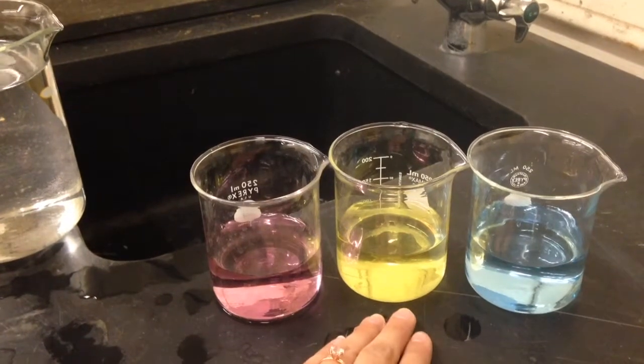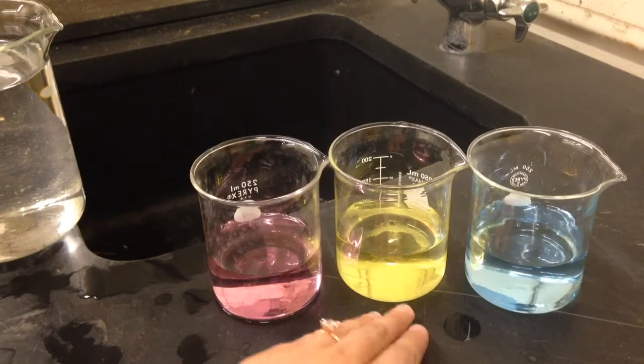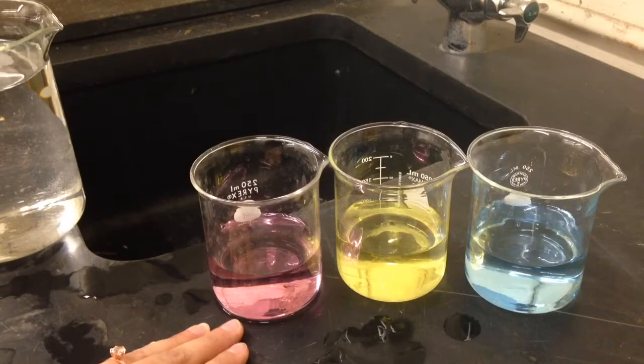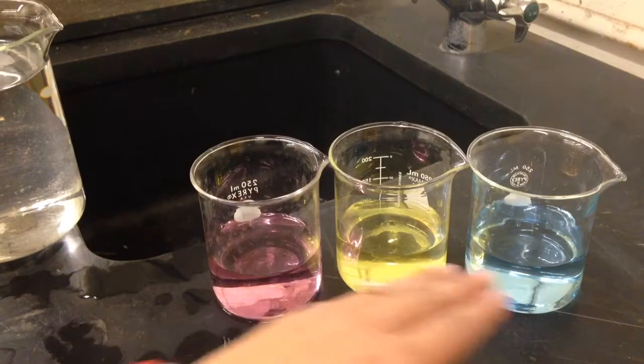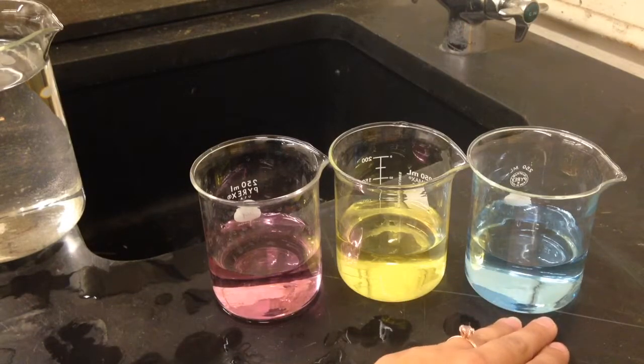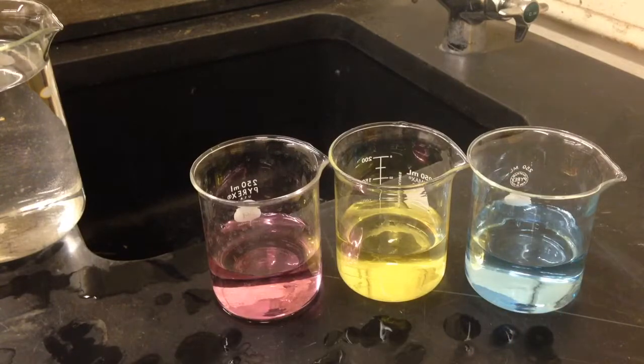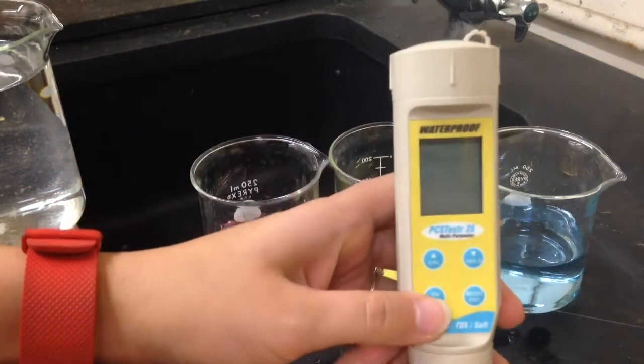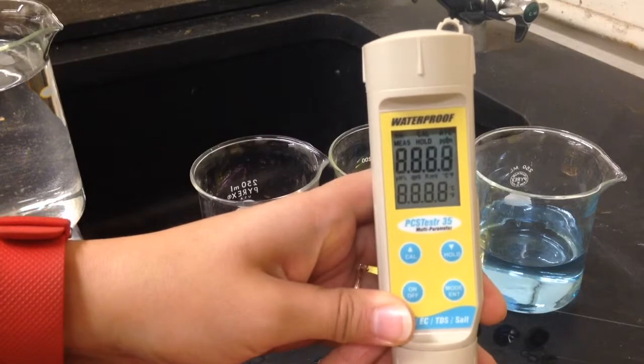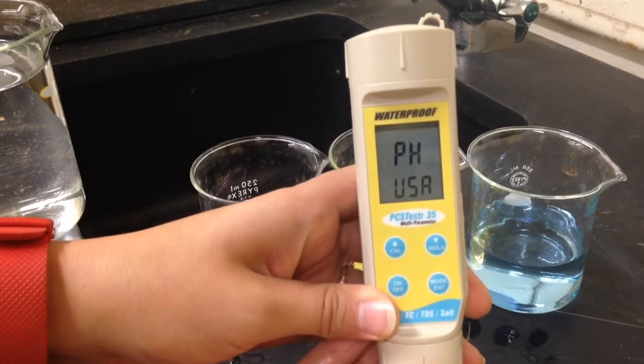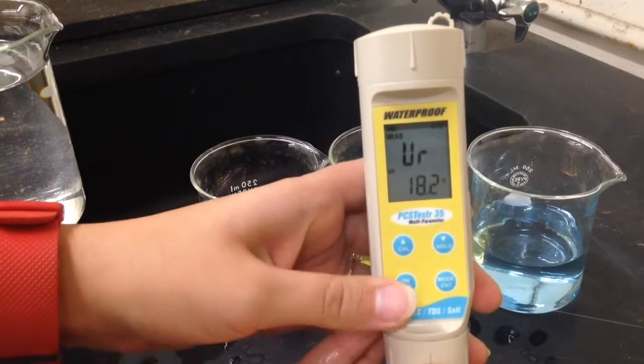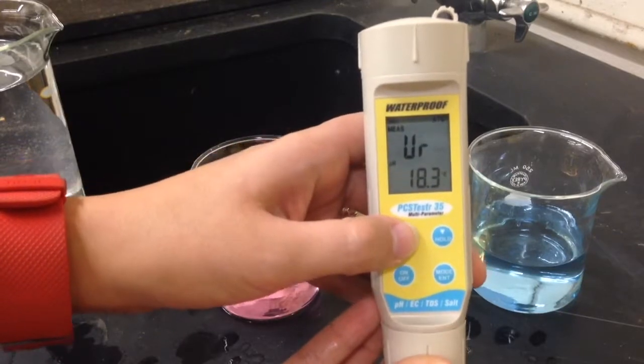We need a neutral solution with a pH of 7, an acidic solution with a pH of 4, and a basic solution with a pH of 10. To calibrate your meter, you need to turn it on and ensure that it is in pH mode. To start the calibration, we're going to push the calibration button.